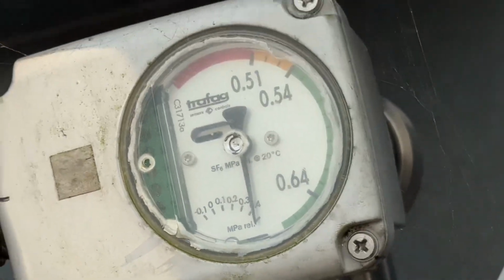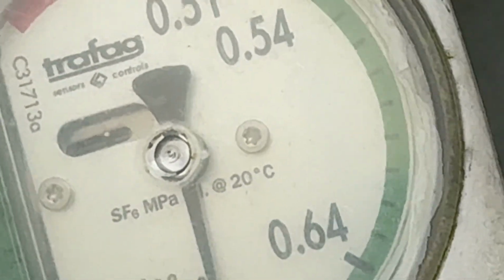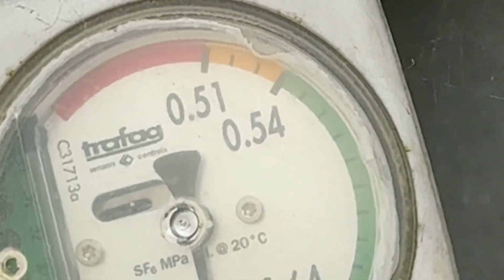Guys, here it is visible that in the yellow zone there are two marks also. From 0.54 there is the first indicating point and the second indicating point. At the first indicating point there is the first alarm, and after that there is a second alarm. Two types of alarm are here. Alarm contacts are here. For the first indication there will be an alarm to the control room, and for the second marking there will also be another alarm. Okay, then let's show another item.